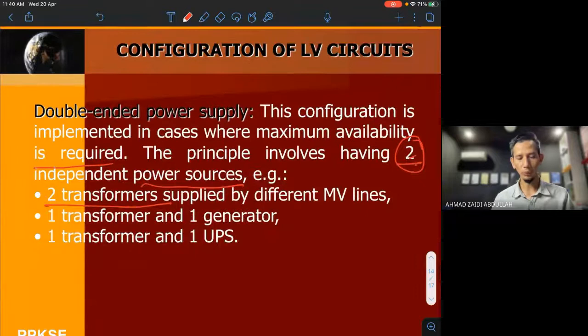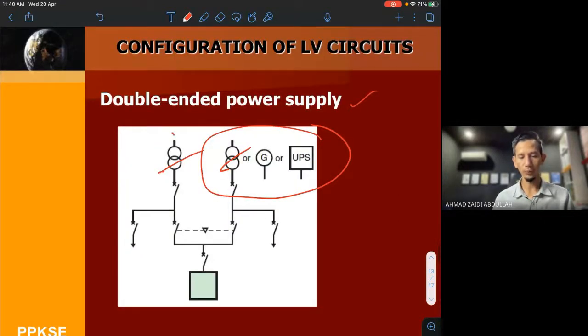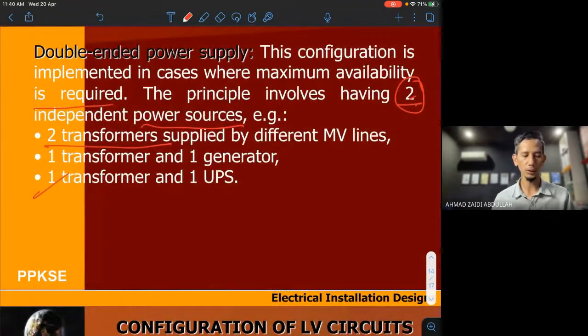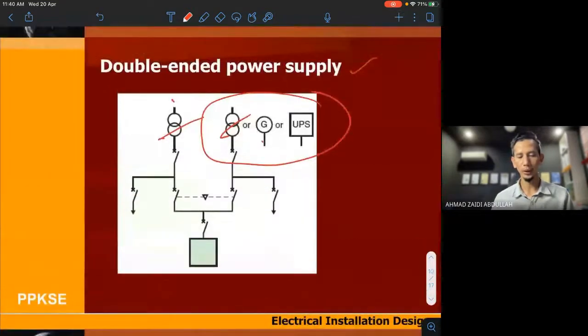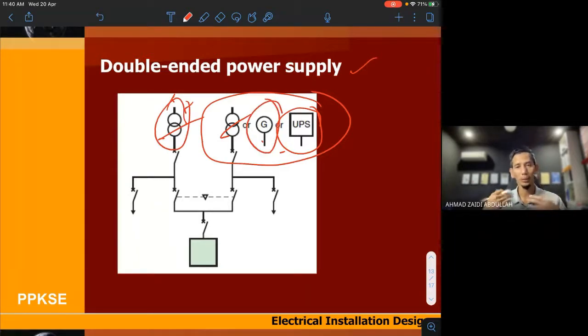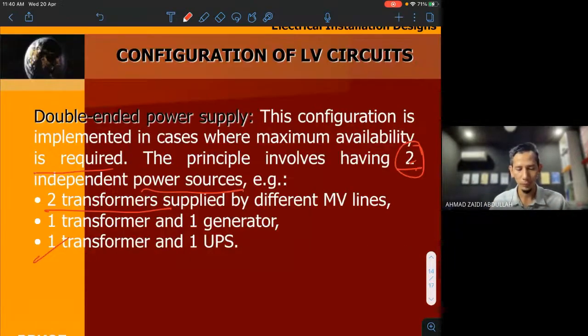Number two, one transformer and one generator. So we have one transformer and another one genset. Then the last is one transformer and one UPS. Maybe we use one transformer and another one UPS. This configuration is normally what we provide in our system. Normally we provide a transformer and a genset to back up our system power supply.